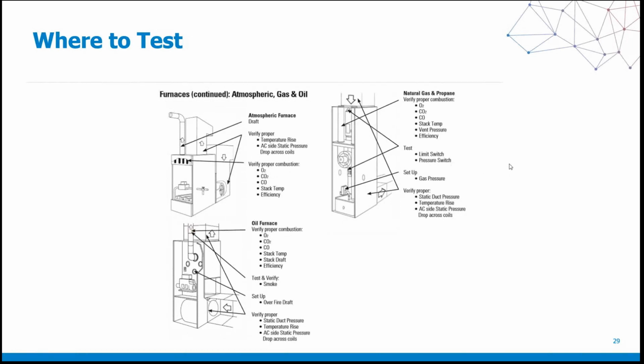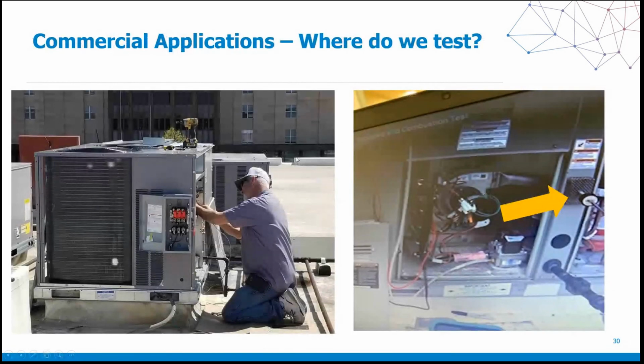And for those of you that work on the commercial side of things and don't think you can test, you can. This nice gentleman here, working out in the hot sun on a rooftop system, you see here, is about to perform a combustion test. And look, here's our vent pipe, and here's where our probe is inserted, right there. So if you don't think you can combustion test a commercial system, you can. I have just as many customers that work on the commercial side of the business as I have on the residential side, and a lot of the contractors I deal with work in both. So it's very important for you to know that for both residential and commercial systems, you can do a combustion test.